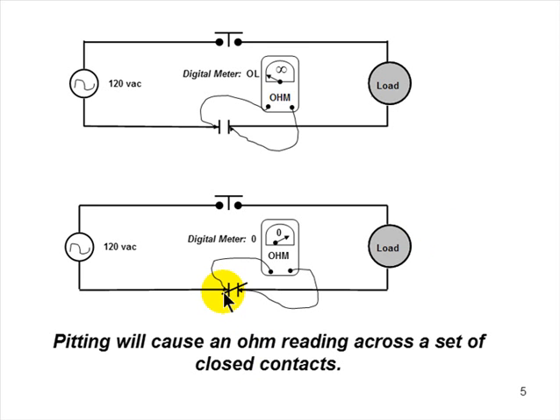That voltage drop is so great that it causes more than a 10% drop here at the load, and that will cause heat, so on and so forth, and it's heat that kills inductive loads. Motors, motor windings, hot, cold. The insulation expands, contracts, eventually cracks, it work hardens, and the windings short out to each other. And you go, oh, I got a short in my winding.